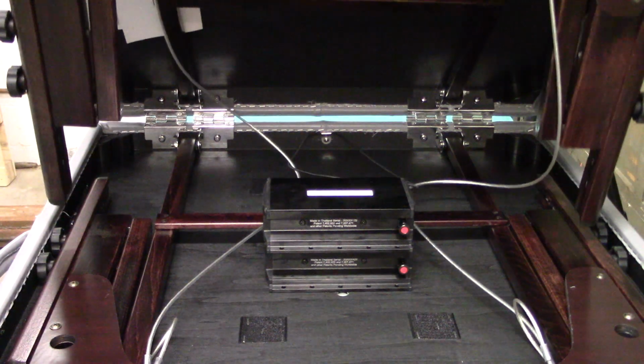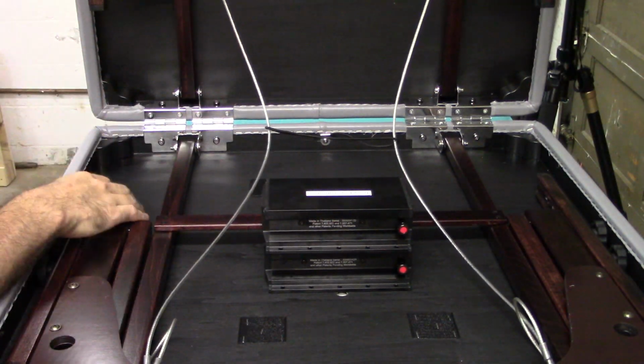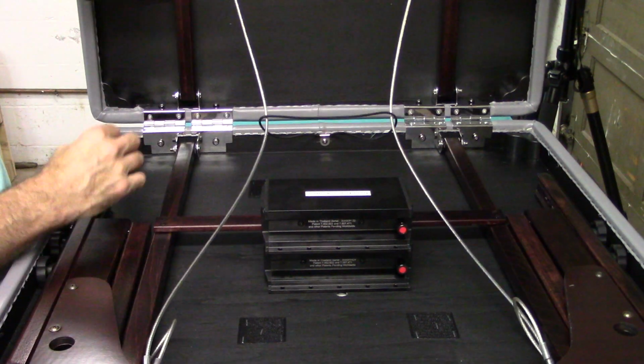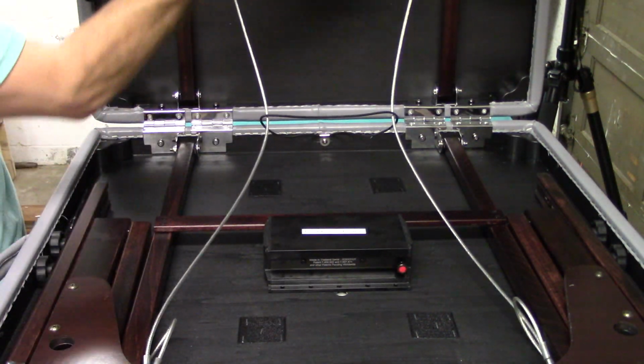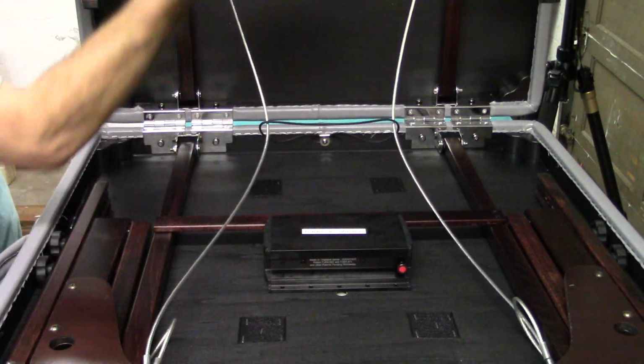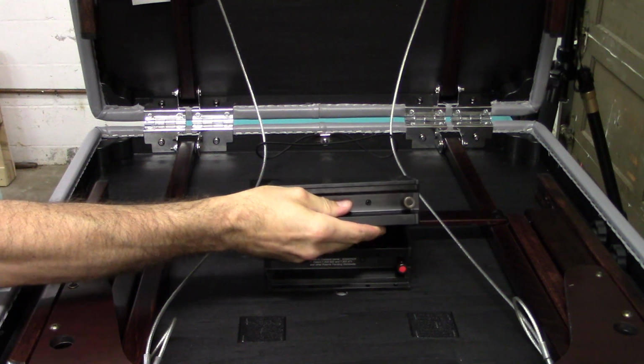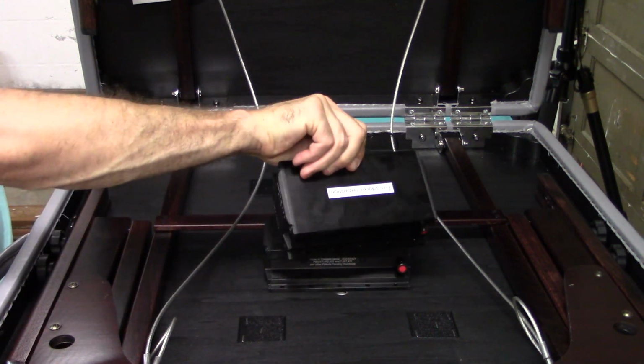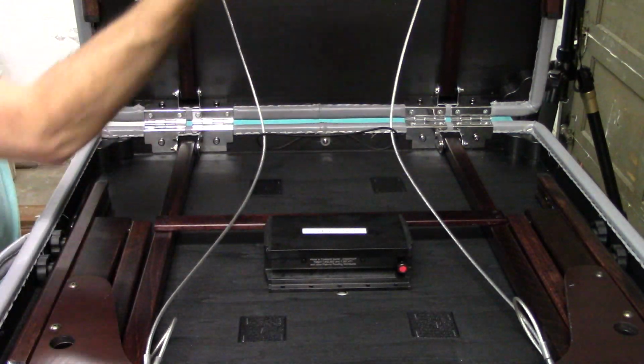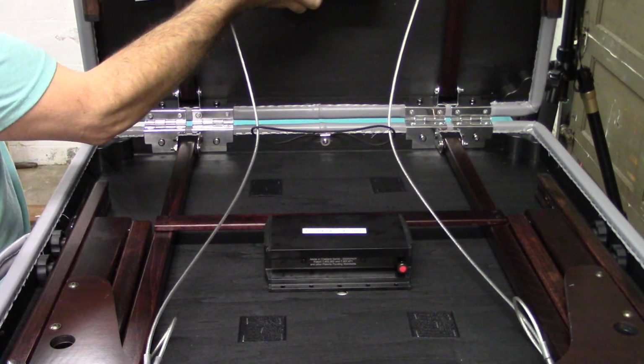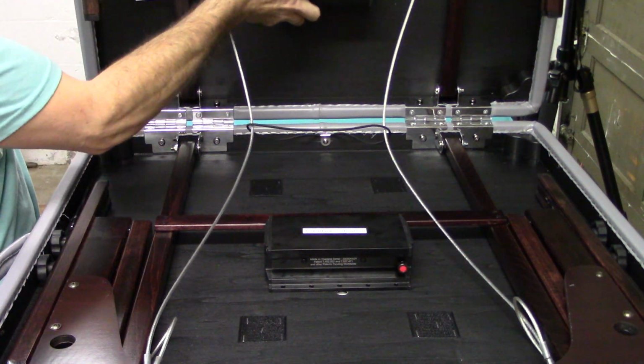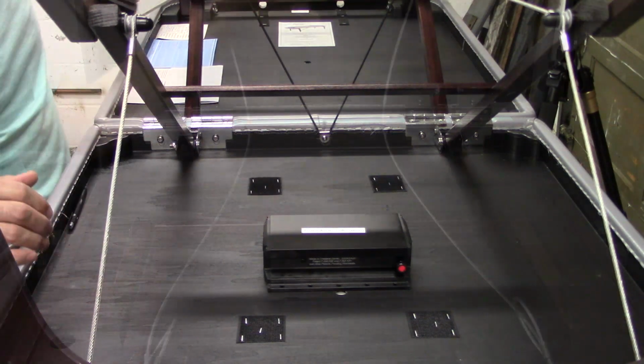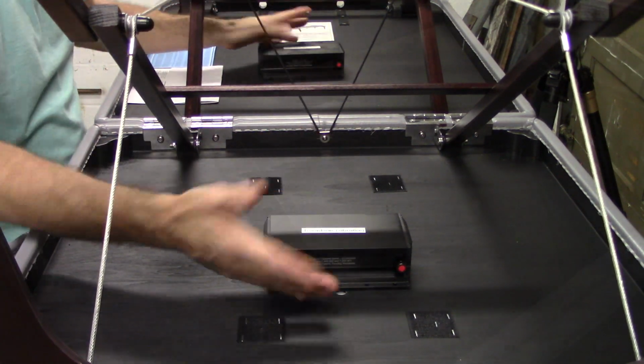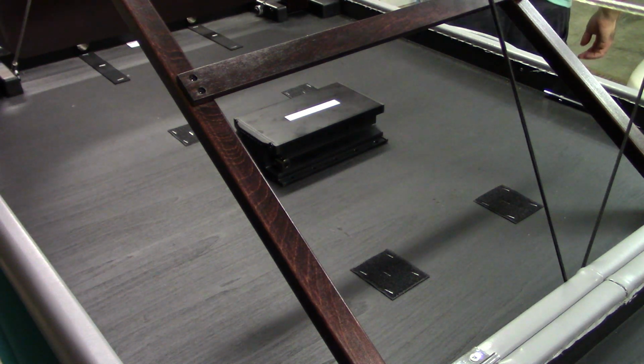And you're going to carefully look inside to see if you have room to close your table. If you do, you can keep your transducers stacked on top of each other. Meaning, when you go to mount, this transducer is going to be mounted up here and this one down here. So as it closes, this one is going to sit right on top of this one. If you don't have room, the one up here is going to be somewhere else, maybe here, maybe further up. We want to try to keep it towards the middle if we can. On this particular unit, we are fortunate enough to mount them in the same spot. So we will start the mounting process now.